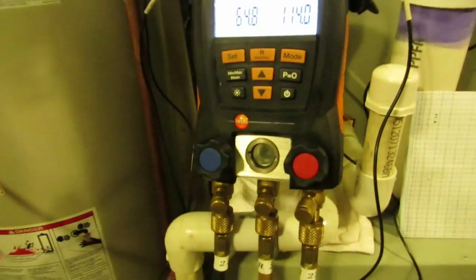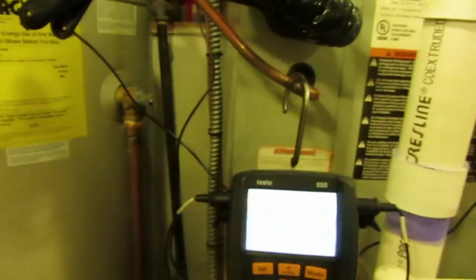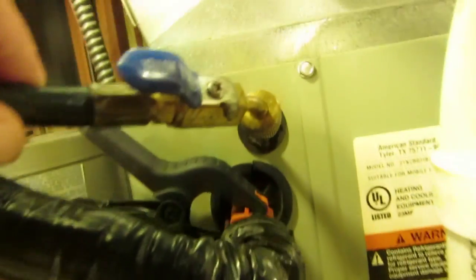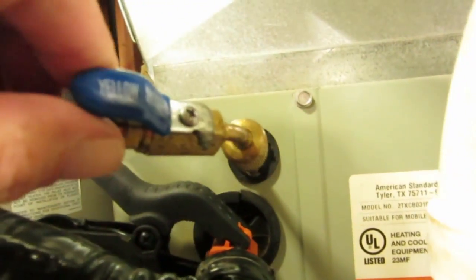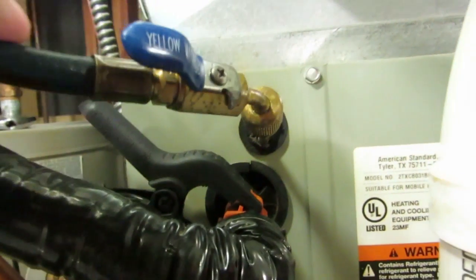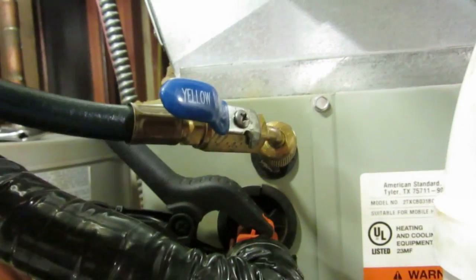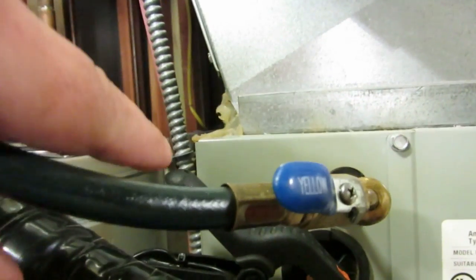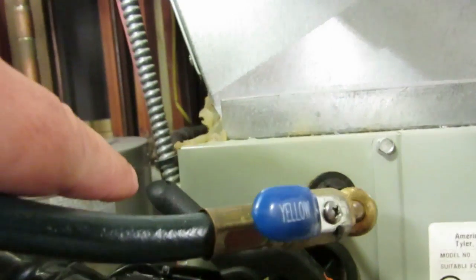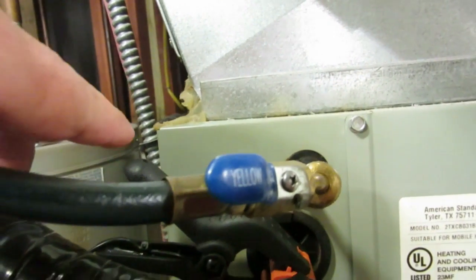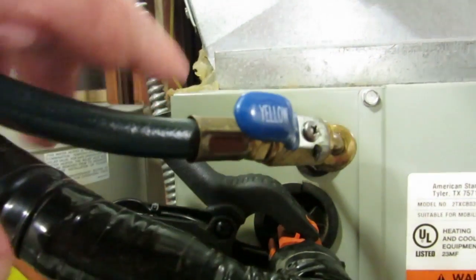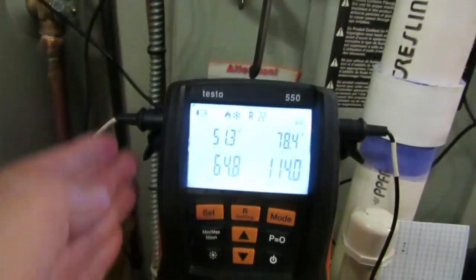Basically what we've done is we've taken the suction side and ran our suction line hose up to our suction line port right here on our American Standard coil, and we removed our CPS compound gauge. We also removed our fill piece with our temperature probe on it and replaced it with our Testo 550 temperature probe which is running back to the suction line of the instrument itself.